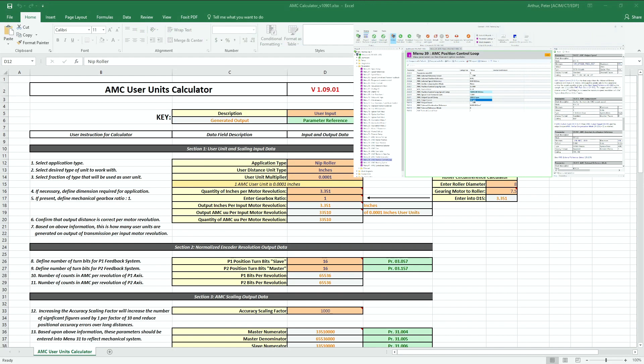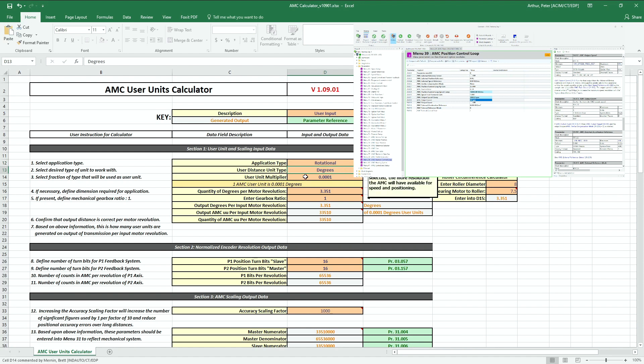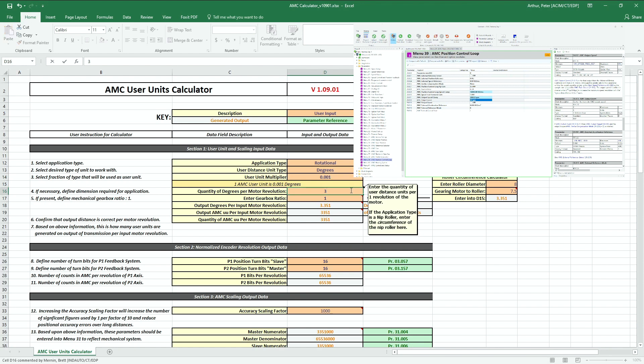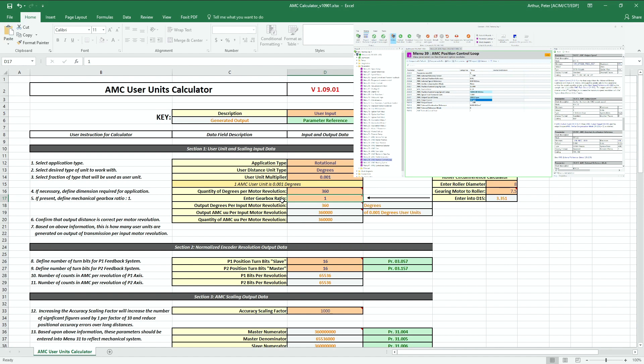Here's the spreadsheet. First, choose your application type — yesterday we used rotational. Then choose your distance units; the AMC doesn't care about this, it's just for your reference, so I chose degrees. The user unit multiplier is the position or distance resolution — how many decimal places you want to use. I tend to use three. Then enter how many degrees per motor revolution: 360.